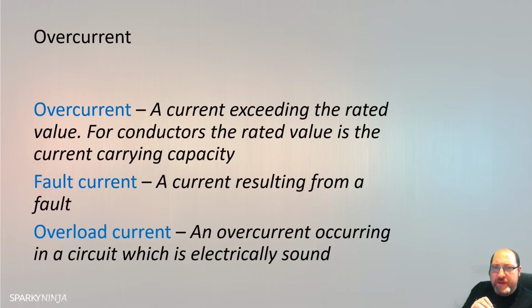So there's a big difference between a fault current and an overload current. When you have a breaker of maybe X value and a cable of X value, an overload current can be anywhere between these gaps or just slightly over that gap. They're not substantially larger, they can be quite large, but normally they're a couple of amps larger. So, as you'll see later on with overcurrent protection, we try to avoid overload currents of long duration.